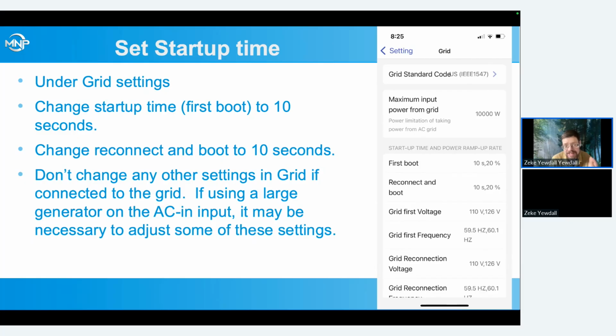One important thing to do in this initial setup is go under grid settings and set up our startup time, our first boot time, and our reconnect and boot time. Otherwise, when we hit that on button, either the physical button on the side of the inverter or the on button in the app, it will count down from 300 seconds, which is 5 minutes, before it turns on. We can set that as short as 10 seconds, and it's a lot less frustrating when you're trying to turn on the inverter and sitting waiting there for it. Don't change any of the other settings in the grid if you're actually connected to the grid. If you're doing things like using a big generator on the AC input instead of grid, or in a lot of the island grids, you will have to adjust some of these settings. But for general US mainland grid, don't change any of these settings.